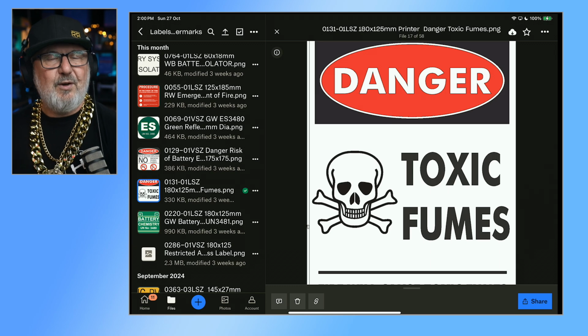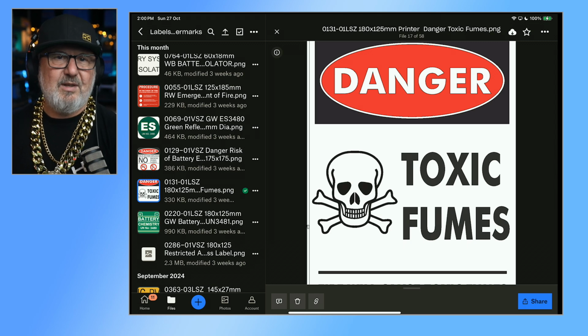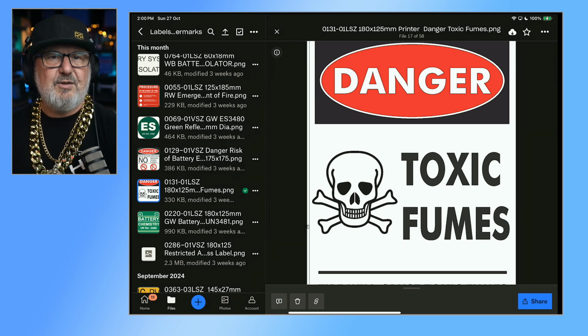But actually that white fog turns into hydrogen fluoride on contact with moist air, which is basically air with any moisture content. So you've now got hydrogen fluoride gas, which is hydrofluoric acid, which is one of the most corrosive acids that is known. It will strip the lining out of your lungs if you breathe it in. So yes, it is definitely a hazard.